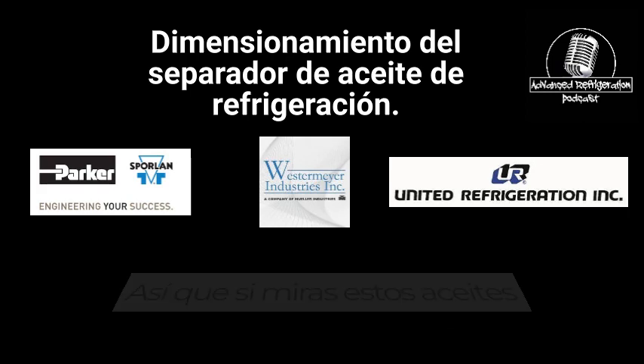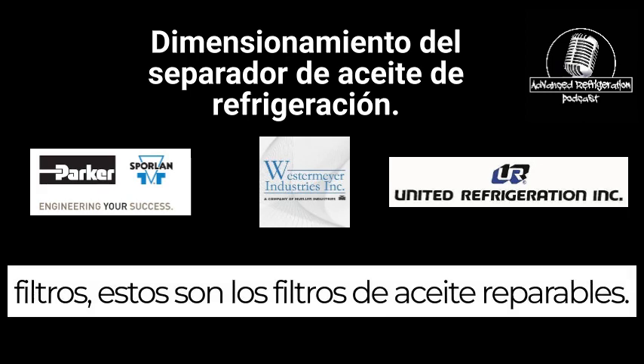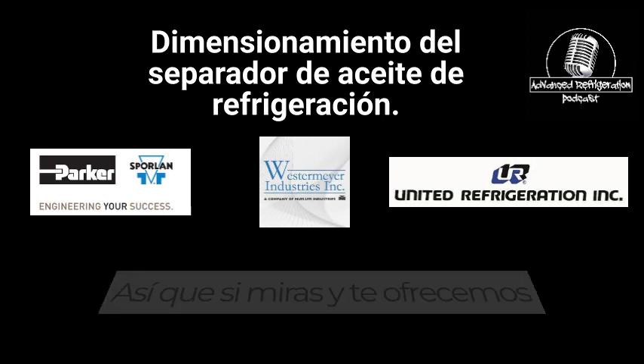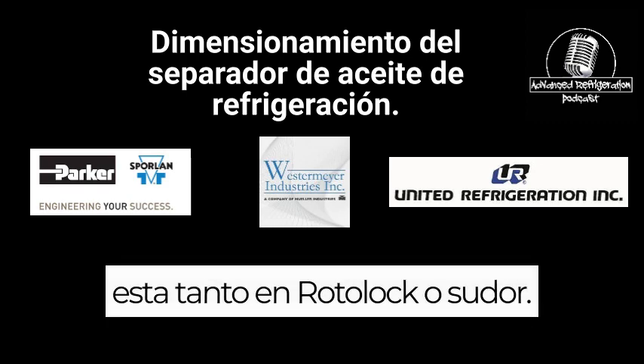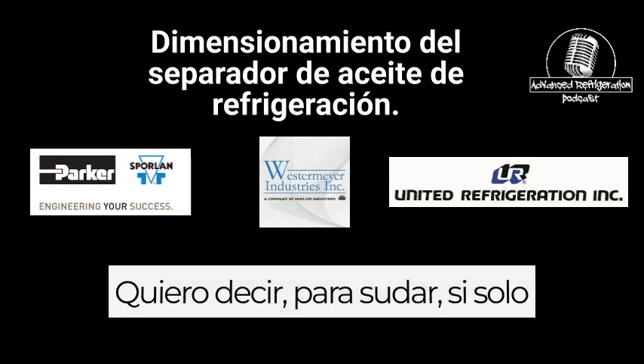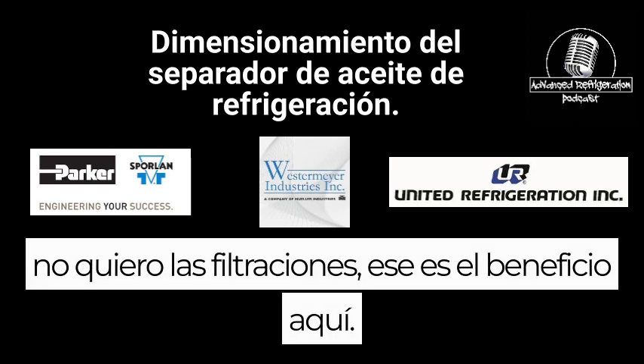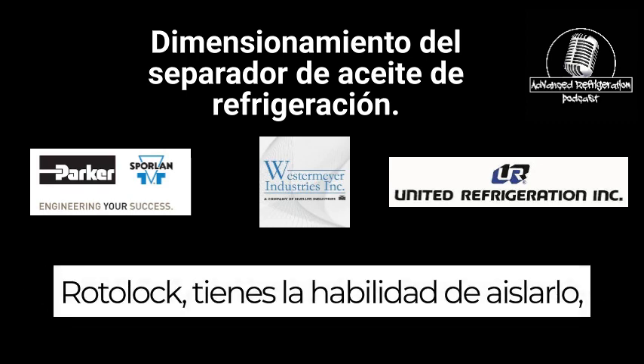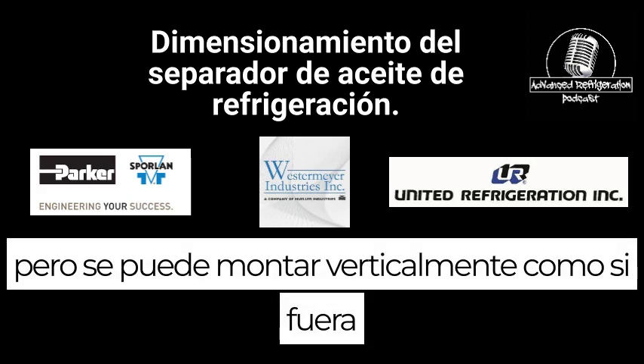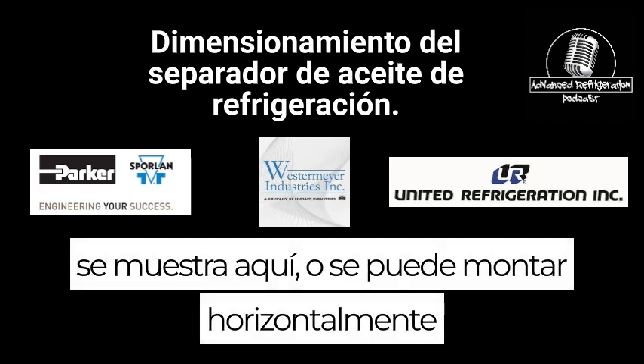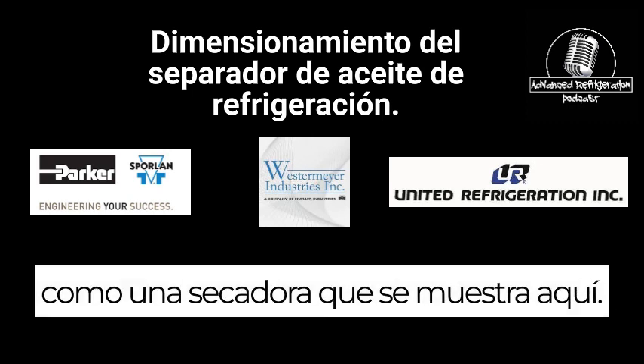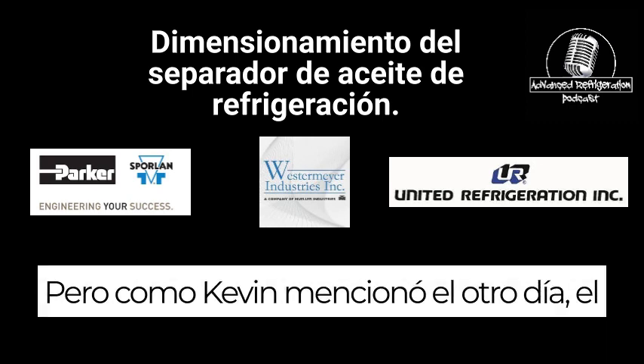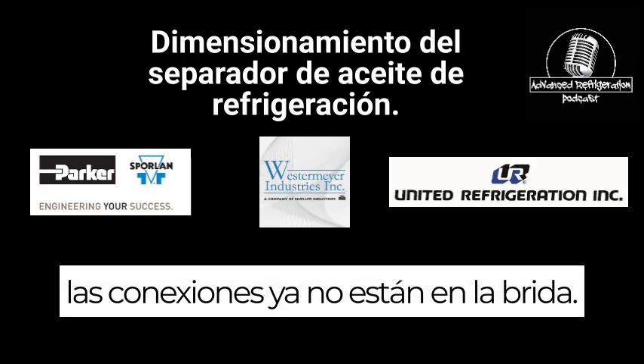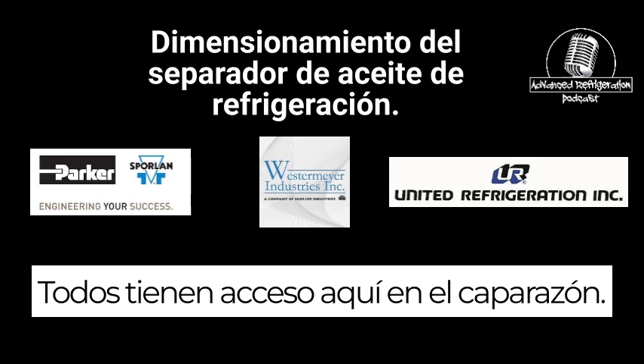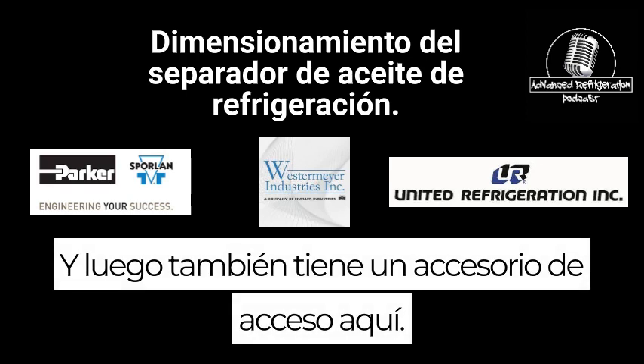Yes, sir. All right. So if you look at these oil filters, this is the serviceable oil filter. We offer this in both Rotolock or Sweat. For Sweat, if you just don't want the leaks, that's the benefit here. With Rotolock, you have the ability to isolate it, but it can be mounted vertically like it's shown here, or it can be mounted horizontally like a dryer. But as Kevin mentioned the other day, the connections are no longer in the flange. They're all in access here on the shell. And then you also have an access fitting here.